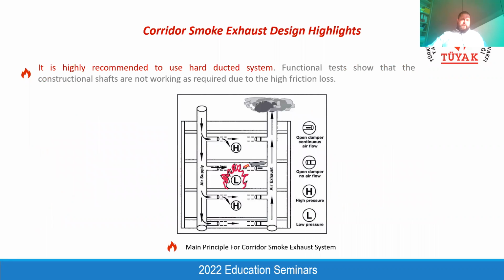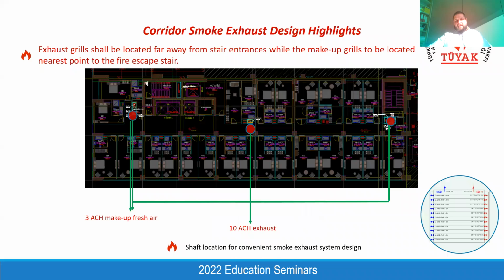And also we have a corridor smoke exhaust system, and as architects we need to pay attention to some points during the design. The general principle is to exhaust smoke from the fire floor and give fresh air to the neighboring floor, so that the smoke will be kept within the fire floor and it will be extracted by the ducts and thrown to the outside of the building, so that the smoke will not propagate to the neighboring areas and to the neighboring floors. This is the main principle.